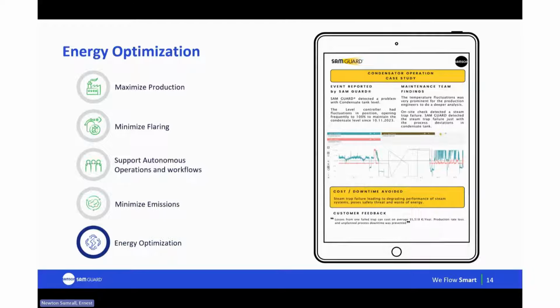So cost and downtime avoided. A steam trap failure can degrade the performance of steam systems, leading to wasted energy and potential safety risks. But thanks to SamGuard's early detection, the issue was resolved before it impacted production or caused unplanned downtime. The customer was really happy by this. They highlighted that a single failed steam trap can result in losses averaging $35,000 a year in some cases. SamGuard's early detection, in this case, prevented both production losses and costly downtime.